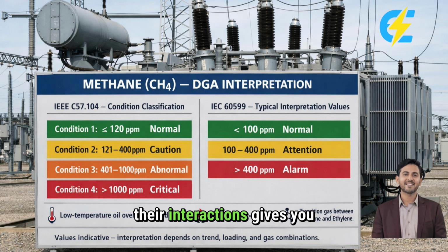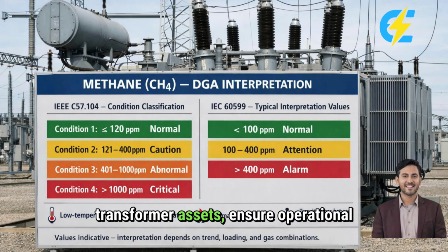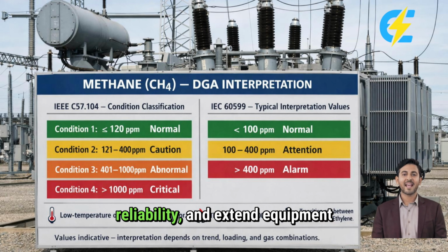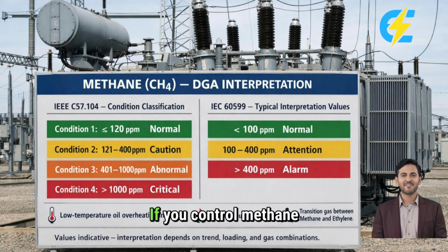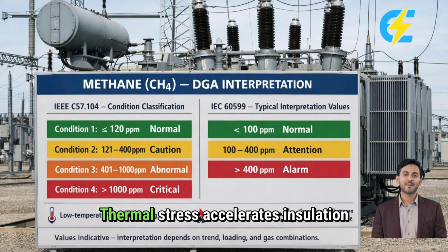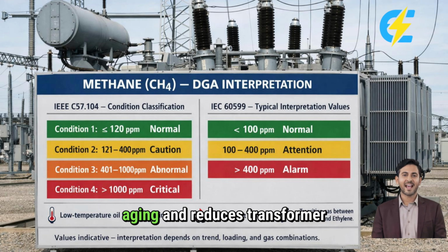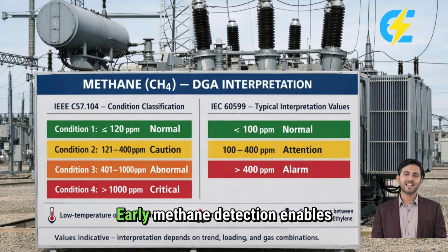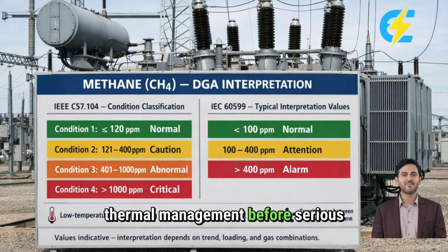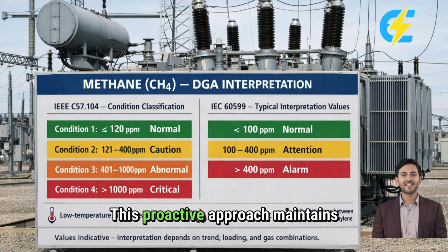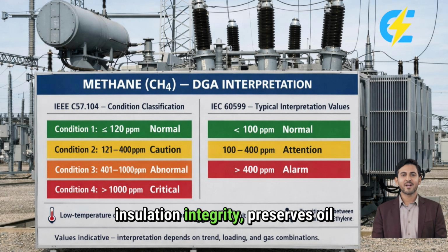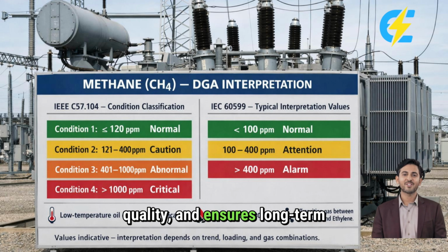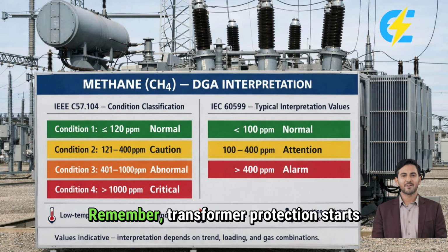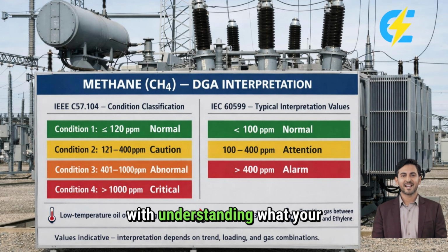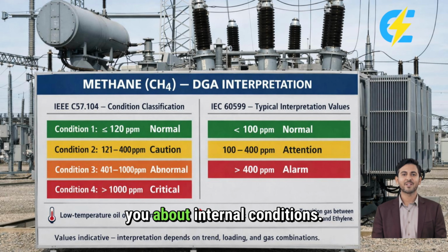Understanding these gases and their interactions gives you the tools to protect transformer assets, ensure operational reliability, and extend equipment life. If you control methane early, you protect oil, paper, and transformer life. Thermal stress accelerates insulation aging and reduces transformer lifespan. Early methane detection enables thermal management before serious damage occurs. This proactive approach maintains insulation integrity, preserves oil quality, and ensures long-term transformer reliability. Remember, transformer protection starts with understanding what your DGA results are telling you about internal conditions.